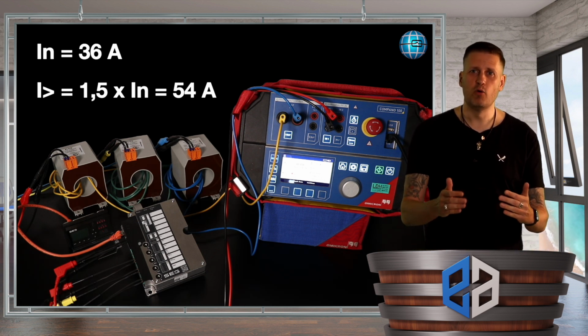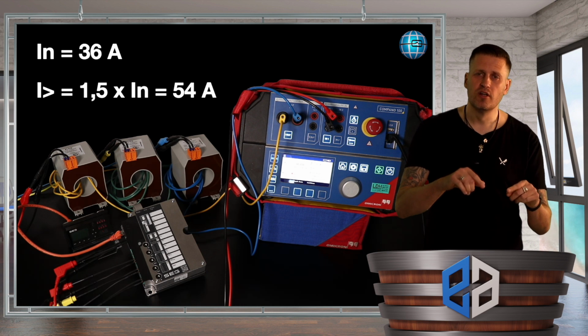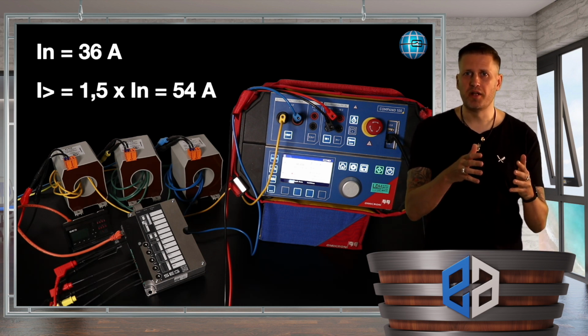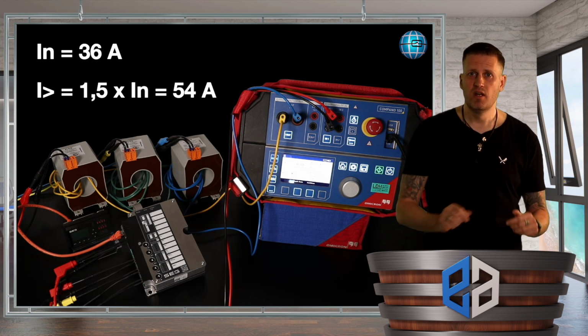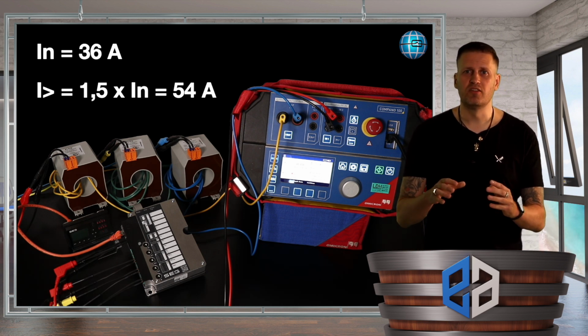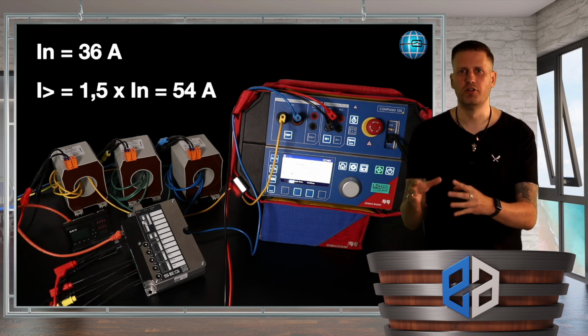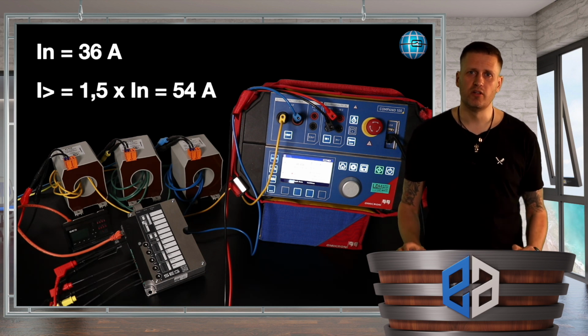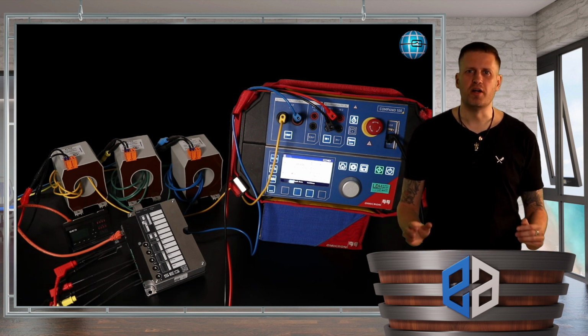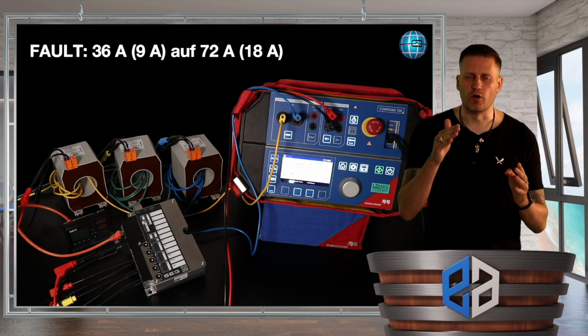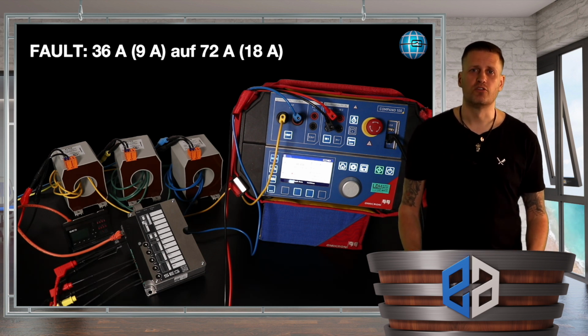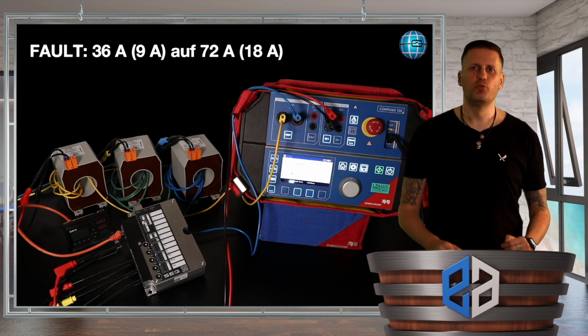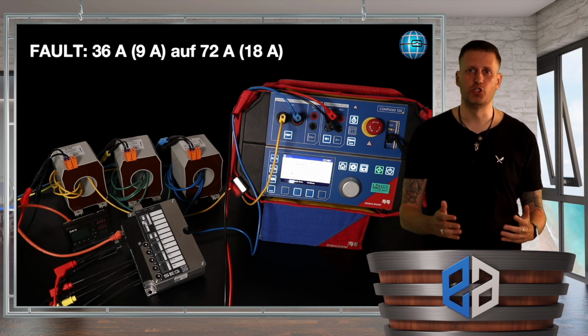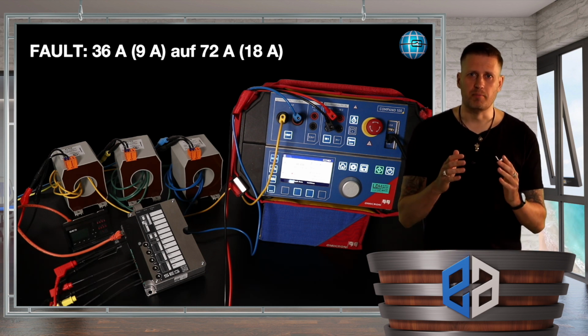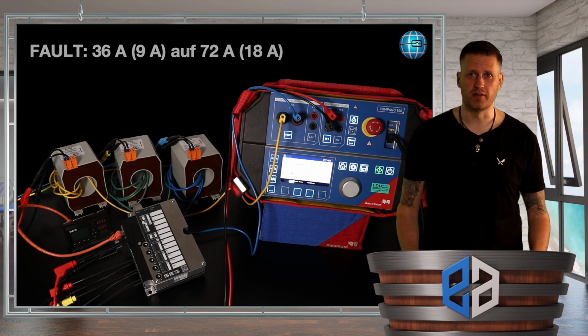As part of our test, we are now interested in the tripping time difference between a short circuit of a relay that is already booted up on the one hand and a short circuit of a relay that is previously in de-energized condition. We want to test with particularly weak currents since this is the much harder case for the relay. Let's get started with a jump from the nominal current to twice the nominal current, which means from 36 amps to 72 amps. Since we wrapped the CTs 4 times, we output a jump from 9 amps to 18 amps and measure the time. Okay, let's push the button.